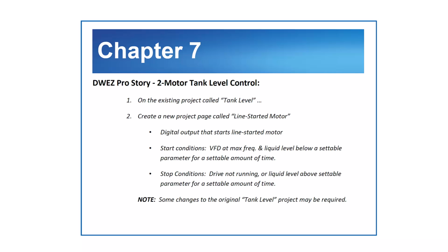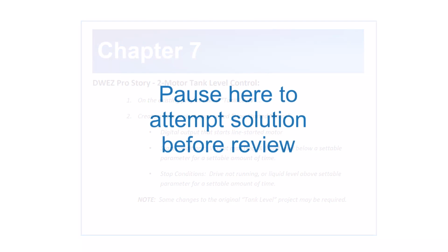On the existing project called Tank Level, create a new project page called Line-Started Motor. There will be a digital output that starts the across-the-line motor. Start conditions include when the VFD is at max frequency and the liquid level is below a settable parameter for a settable amount of time. The stop condition will be that the drive is not running or the liquid level is above the settable parameter for a settable amount of time. Note that you may need to make some changes to the original tank level project page.